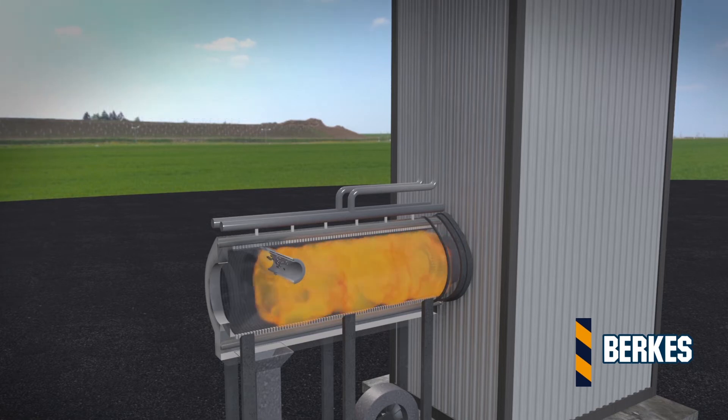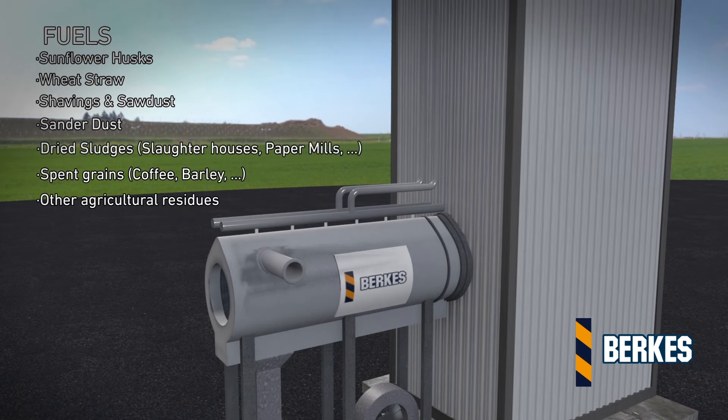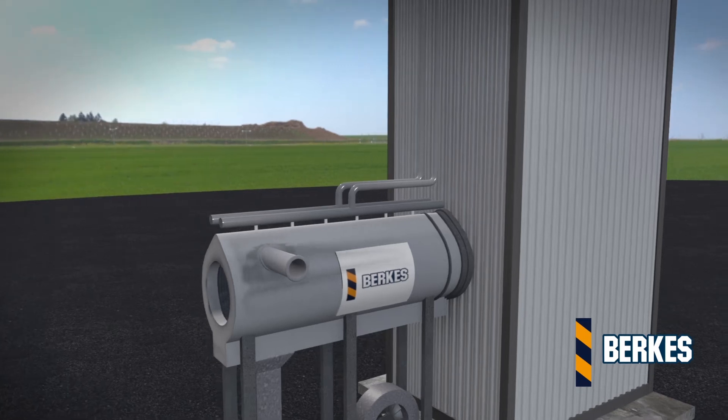The system allows great flexibility, burning a wide range of fuels and being able to mix them upon availability. Load modulation rate is determined by the fuel injection, which can be varied or turned off quickly with negligible thermal inertia.